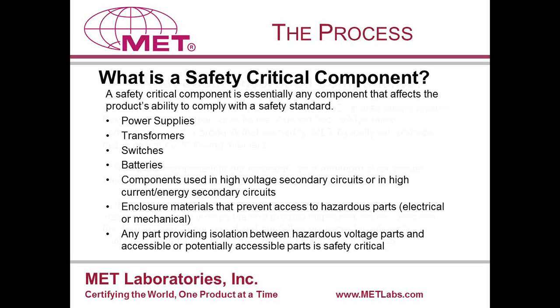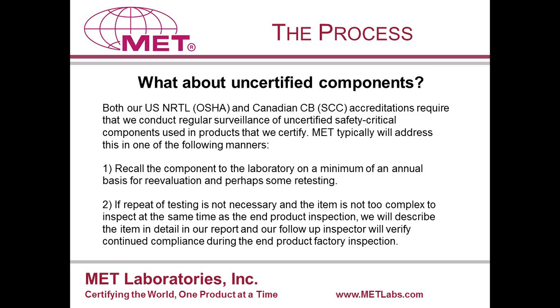In Europe, very often manufacturers will want to use components that have only a CE mark. This will not be adequate for products that enter North America. If a product is on the list of safety critical components, they must have an NRTL listing or recognition. A CE mark is not enough. In fact, the CE mark means nothing in the United States.